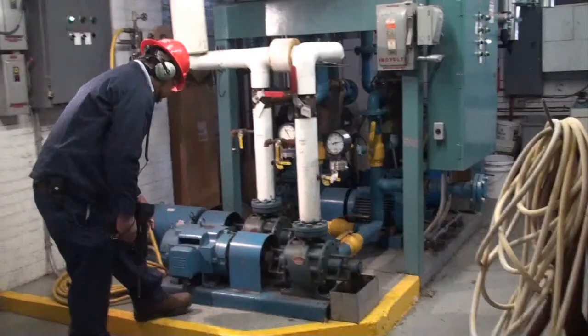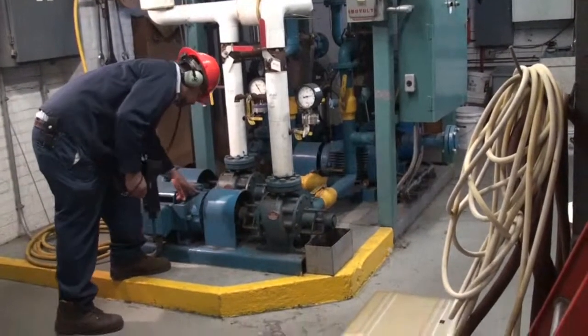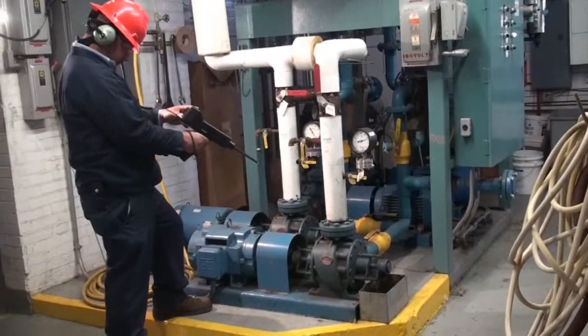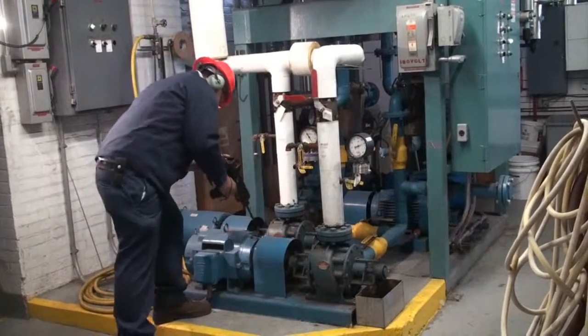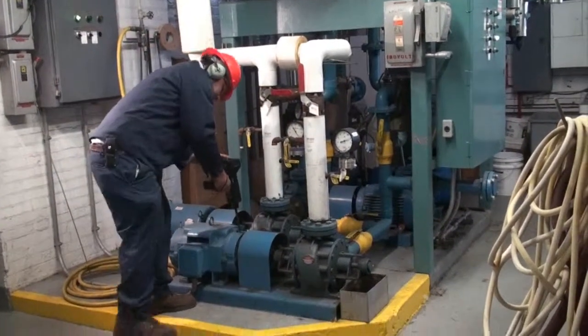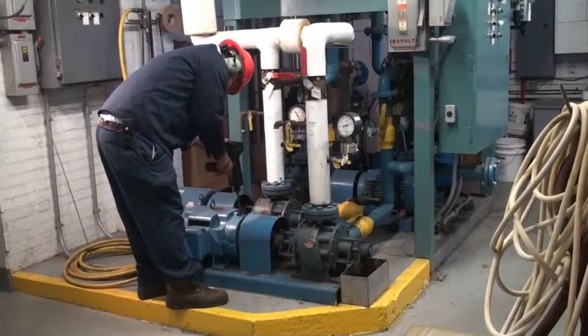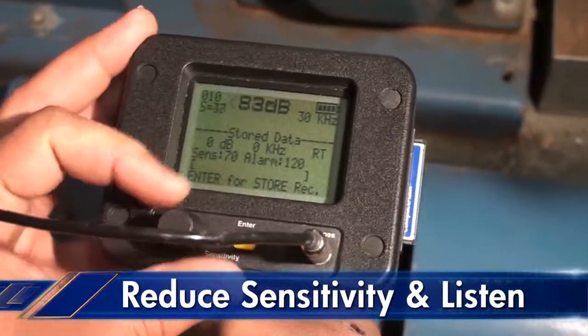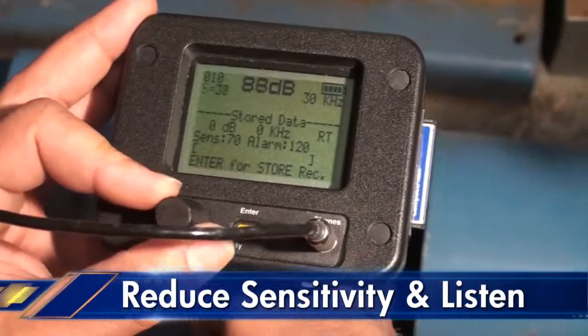Now let's go and check a bearing. First, we'll check the identification tag to see if it conforms to the test number in our route. Then we'll touch the bearing and reduce the sensitivity to hear the bearing more clearly.